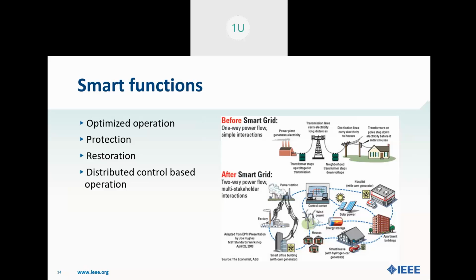In addition, IEDs also help in protection. One backup IED is able to replace various primary protection IEDs. One protection IED receives data regarding the protection target of the IED through calculation and communicates by itself when a measurement device stops functioning. The next smart function is restoration.